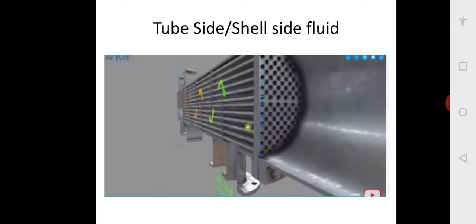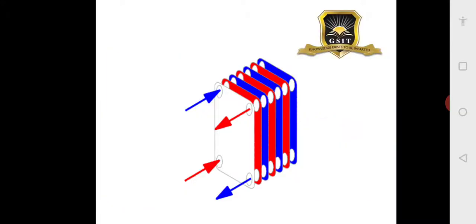By comparing the plate type and shell and tube type exchangers, you can see that the surface area A is increased. In convection, Q = H × A × ΔT. We cannot change ΔT since the temperatures of hot and cold fluid are fixed, but we increase the contact surface area A between hot and cold fluid. So because of this increase in A, the rate of heat transfer Q increases. Not only is A increased, but H — the convective heat transfer coefficient — is also increased.